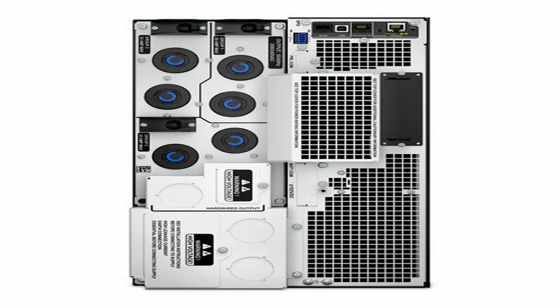Intelligent battery management might sound like a buzzword, but it's actually a set of algorithms that monitor temperature, charge cycles, and health to optimize the charge/discharge curve. In a 24/7 operation, batteries degrade faster if they're constantly overcharged or left in a high-temperature environment. This UPS talks to the batteries, throttles charge when they're warm, and alerts you via SNMP or the web interface when a module is approaching end of life. The practical upside is you get a longer battery lifespan, fewer surprise replacements, and a clear maintenance schedule that you can plug into your existing ticketing system.